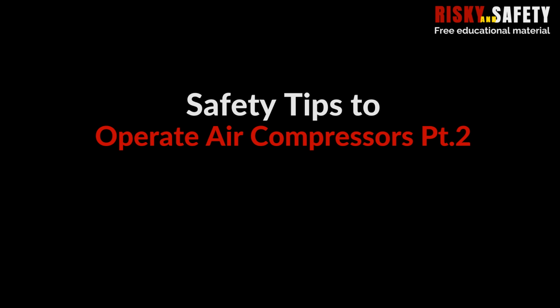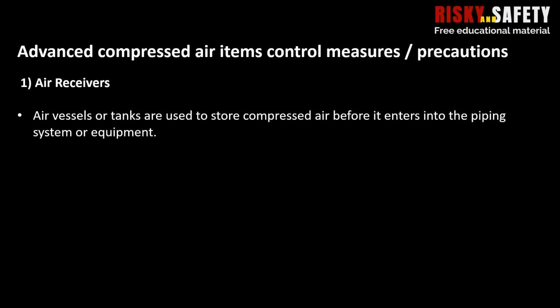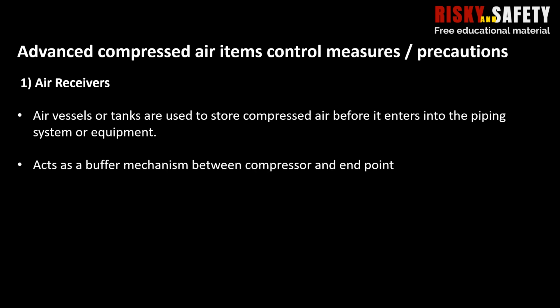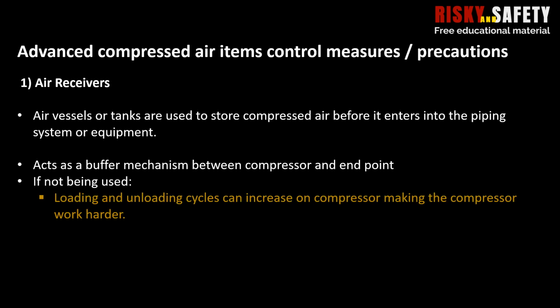Air receivers. Air vessels or tanks are used to store compressed air before it enters the piping system or equipment. Simply, it acts as a buffer between the compressor and the endpoint where compressed air is demanded, and without it, loading and unloading cycles can increase on the compressor, making the compressor work harder.